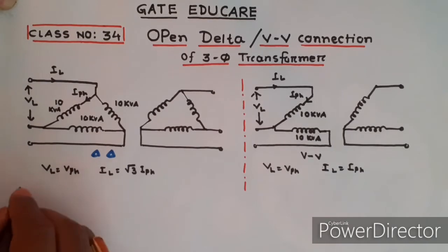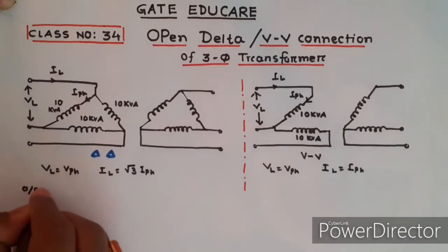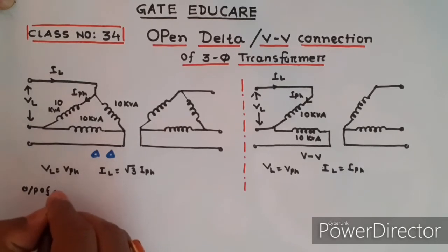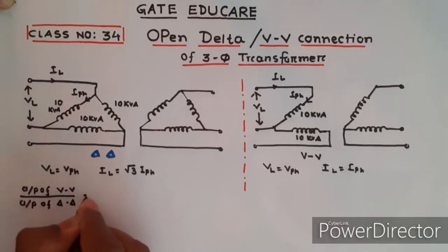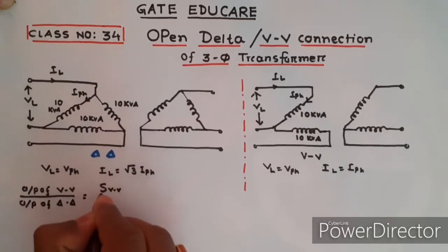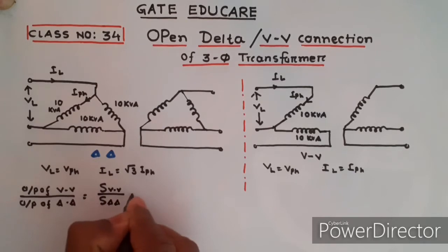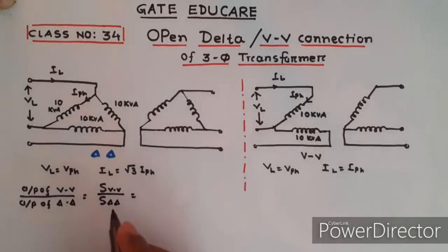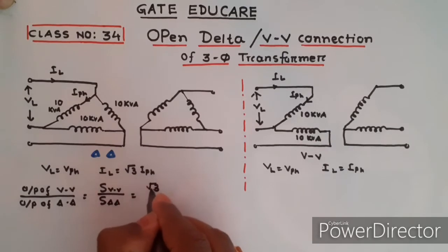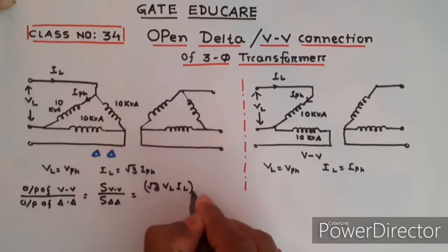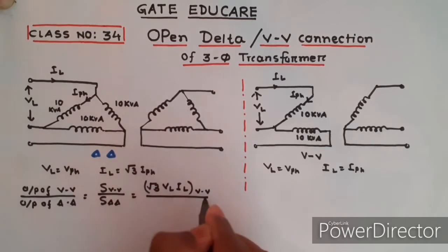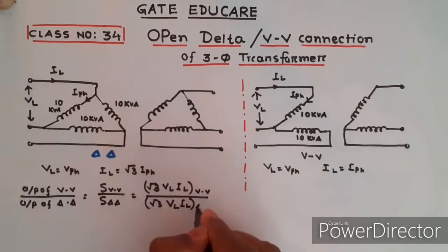Now the output ratio: output of V-V connection divided by output of delta-delta connection equals kVA of V-V divided by kVA of delta-delta. The kVA is given by root 3 times VL times IL, applied to both the V-V connection and the delta-delta connection.